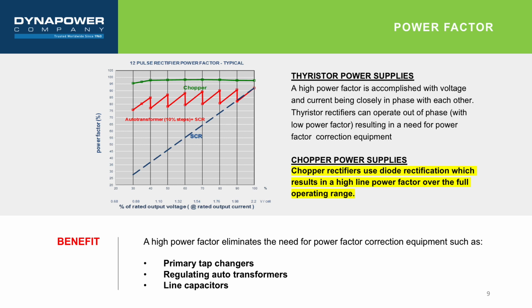Typical chopper system power factors run at 0.925 to 0.95, with transformer K factors of 2 to 3, resulting in lower transformer losses. Typical thyristor rectifiers run at power factors in the range of 0.85 and K factors of 12 to 20, thereby increasing the line and transformer losses.